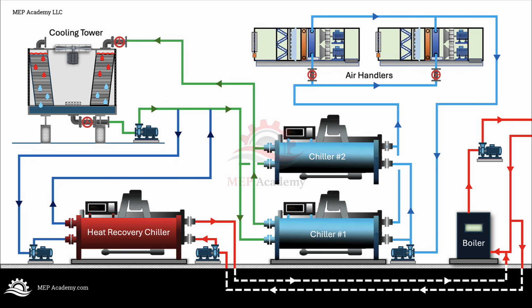This type of application can make sense in a large central plant where the facility has both cooling and heating needs throughout the year. A hospital is a good example. Hospitals often have interior cooling loads from people, lights, medical equipment, imaging rooms, laboratories, and ventilation requirements. At the same time, hospitals may need hot water for reheat coils, domestic hot water, perimeter heating, and air systems that maintain pressure relationships between spaces. Without heat recovery, the hospital may reject heat through the cooling towers while the boilers are operating to provide heat somewhere else.